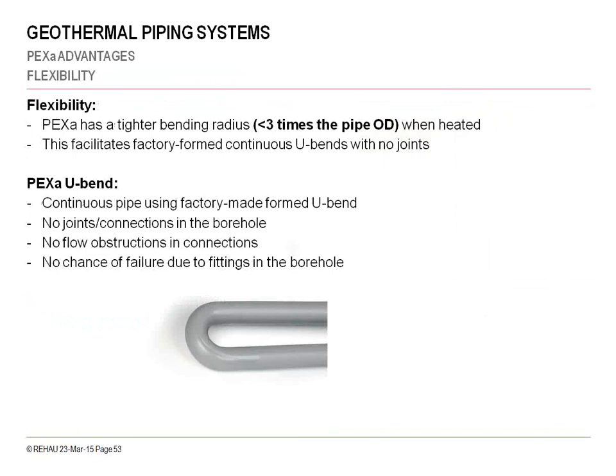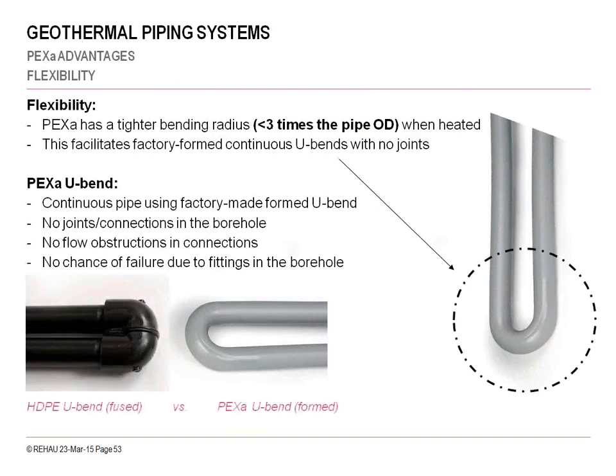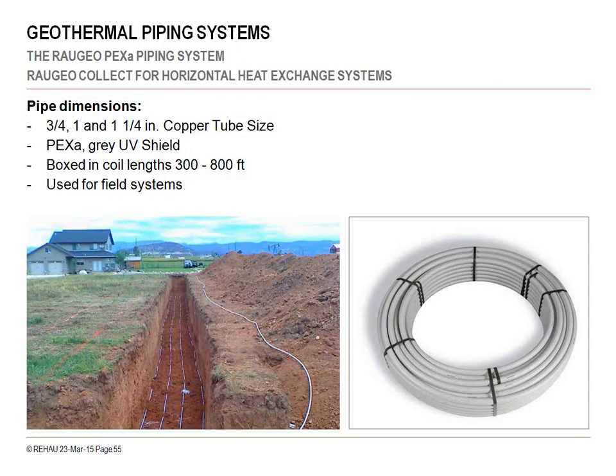Back to that bend radius. As I mentioned, we can get down to 5 times the OD without kinking of the pipe. If we put a little heat to it in a controlled environment, we can get down under 3 times the OD of the pipe dimension. And what we're seeing here is a U-bend, because of that tight bend radius. We are able to take the joint out of the vertical loops where the HDPE is welded, as you can see on the left there. We also have coil pipe in PEX-A for horizontal applications in different sizes and different coil lengths.